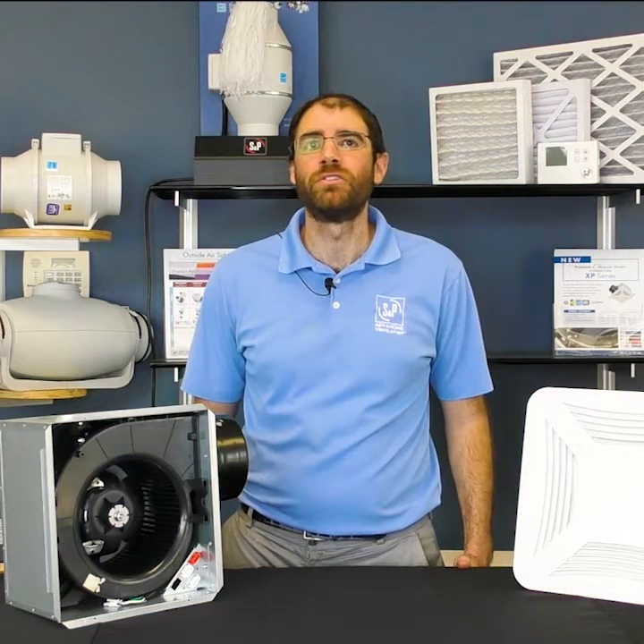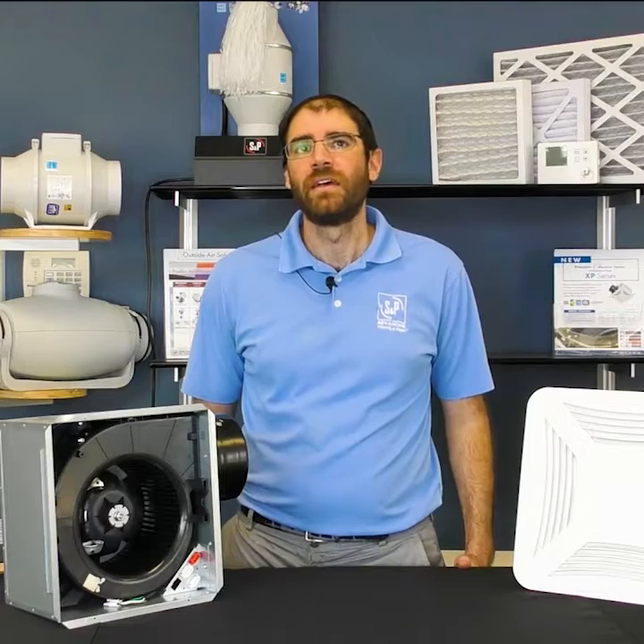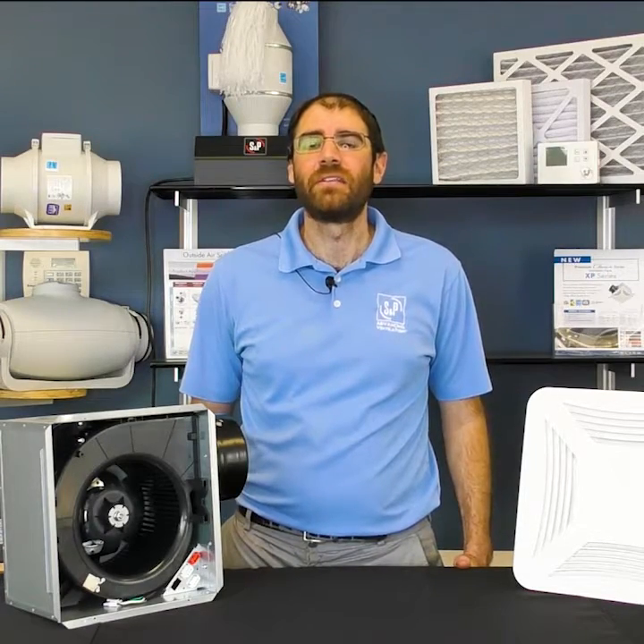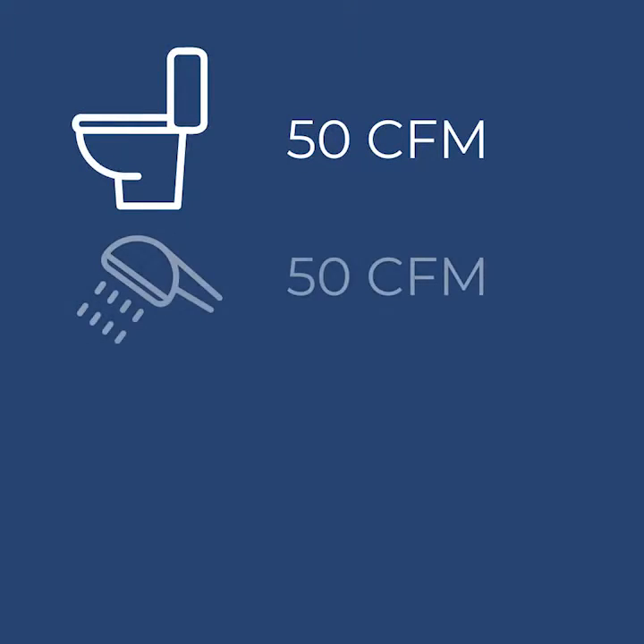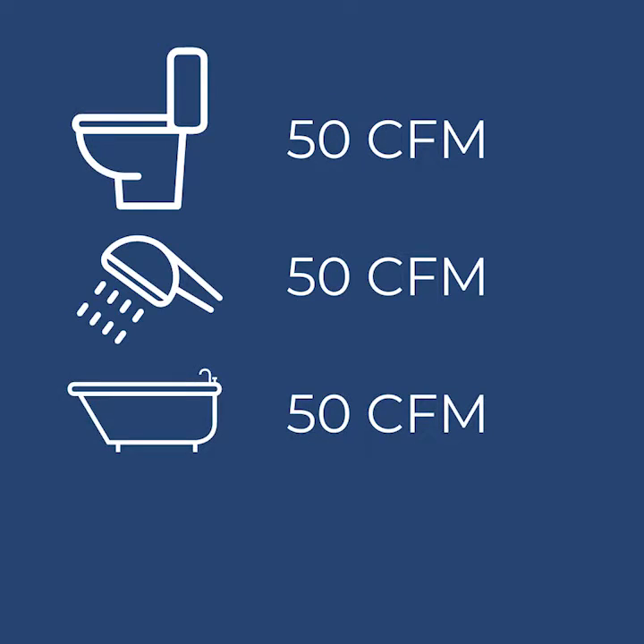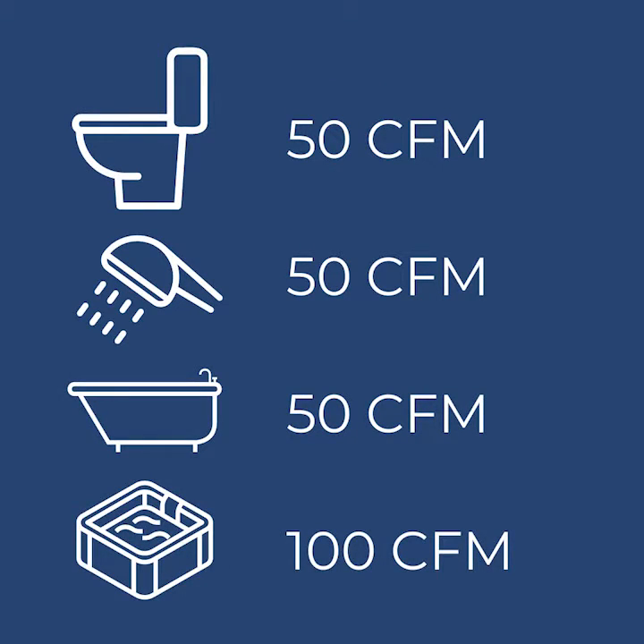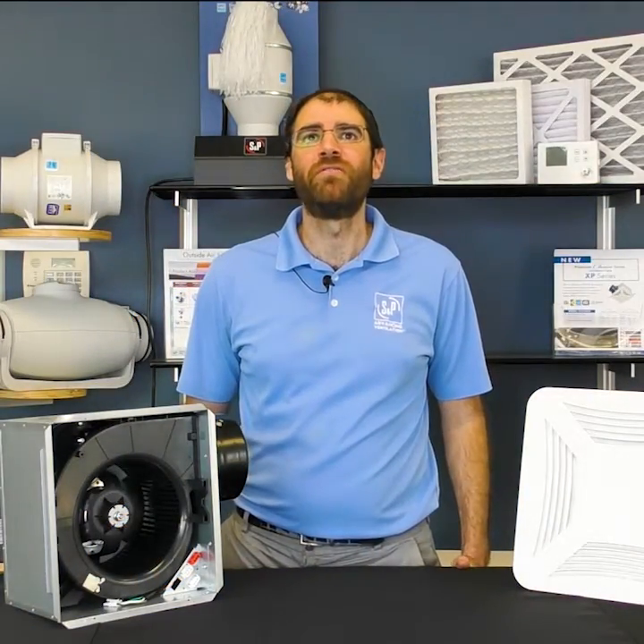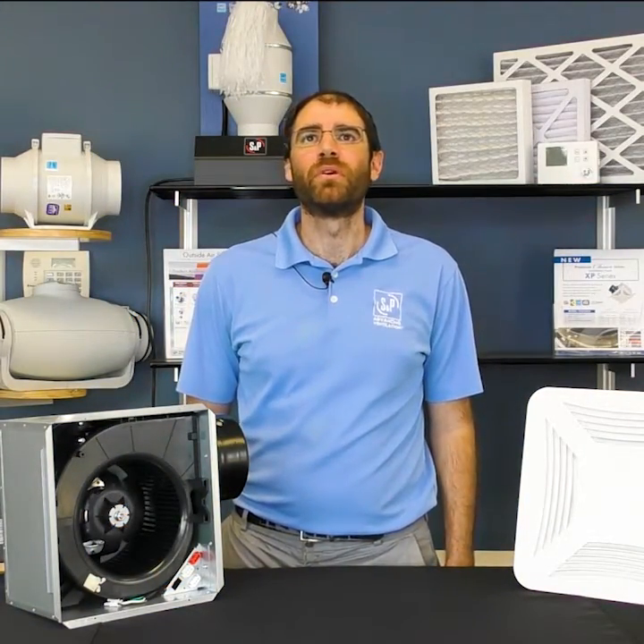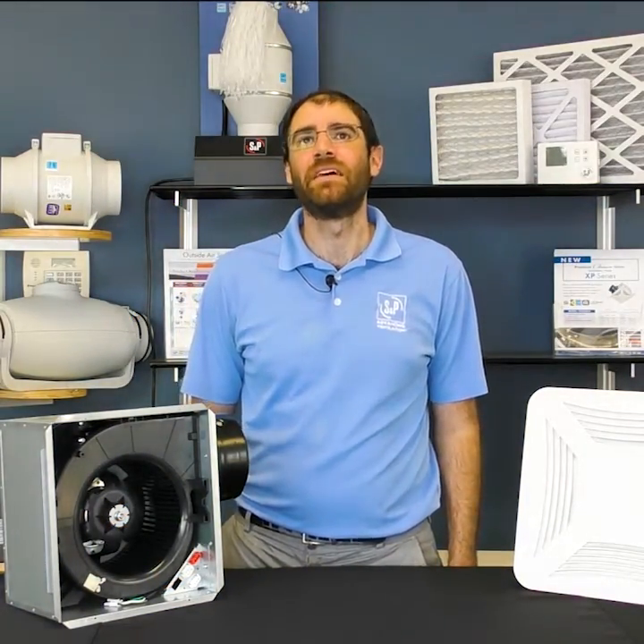If your bathroom is over 100 square feet, the CFM needed is calculated based on the fixtures in the bathroom. For example, a toilet requires 50 CFM, a shower 50 CFM, a bathtub 50 CFM, and a jetted tub requires 100 CFM. Add the CFM of all the fixtures within the bathroom for the required fan CFM.